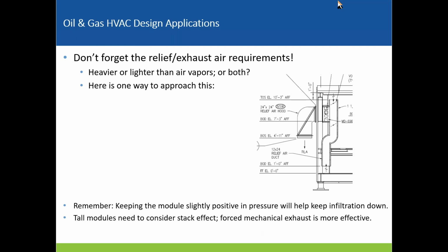Then we have to worry about the relief and exhaust air requirements. We need to know, and Eric mentioned this, heavier or lighter than air vapors or both, propanes or methanes. One thing that we like to do, I just showed an example of an option you could do for a short module. I wouldn't recommend this for a sea-lift module because the stack effect is actually pretty impressive on anything that's probably over 12 feet.